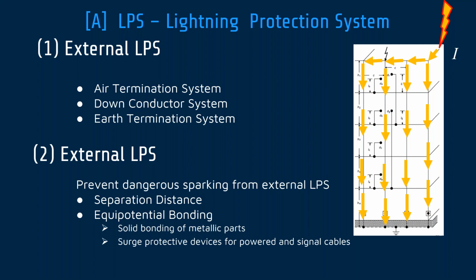Now, when we bond, as per SANS 10142-1, when we bond all the systems, the earths of different systems together, and we have to bond the lightning protection system's earth to the main electrical installation earth, what we're doing is we're bringing the voltage that is on the lightning protection system earth point into the DB of the electrical system. And so we now sit with a situation of 220 or 400 volt phase voltages that we've got to clamp.